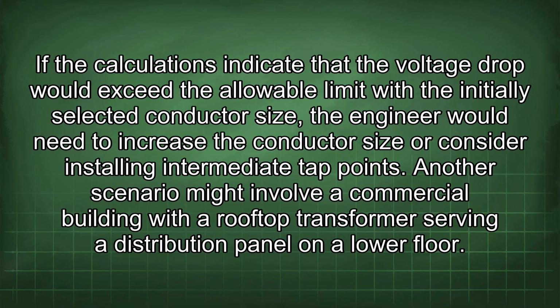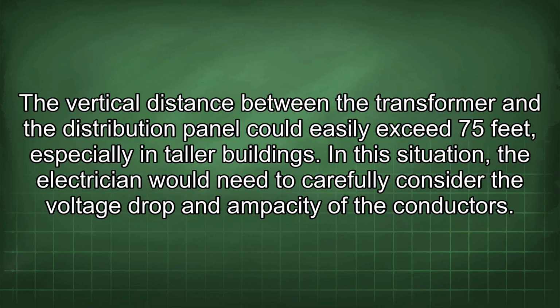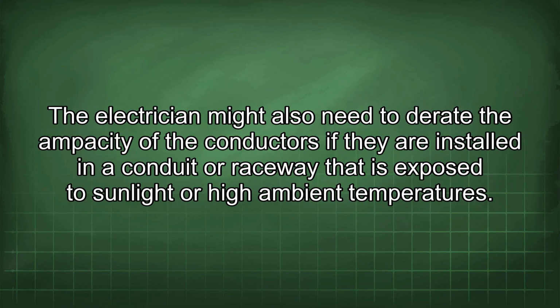Another scenario might involve a commercial building with a rooftop transformer serving a distribution panel on a lower floor. The vertical distance between the transformer and the distribution panel could easily exceed 75 feet, especially in taller buildings. In this situation, the electrician would need to carefully consider the voltage drop and ampacity of the conductors. The electrician might also need to derate the ampacity of the conductors if they are installed in a conduit or raceway that is exposed to sunlight or high ambient temperatures.